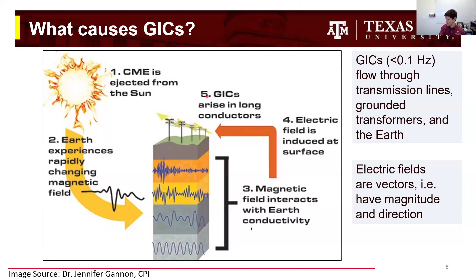I'll mention one more thing, then pause for initial questions. As I mentioned, the GMD causes geomagnetically induced currents, or GICs - this is a high-level picture of what I just described. Since changes in Earth's magnetic field are fairly slow compared to the 60 hertz power system frequency, they're pretty low frequency, sub 1 hertz - like 0.1 and lower.